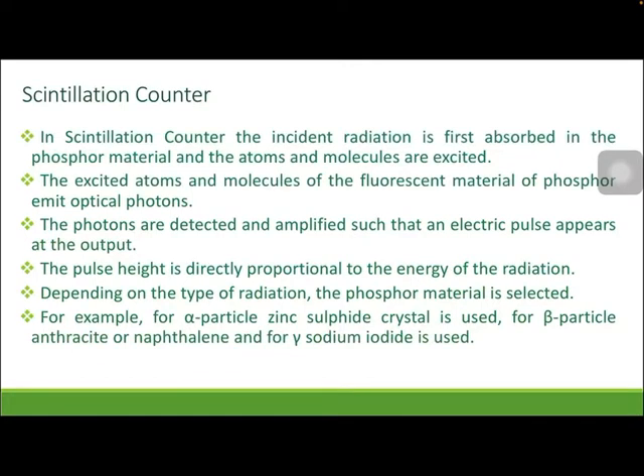The principle of the scintillation counter is: the incident radiation is first absorbed in the phosphor material and the atoms and molecules are excited. The excited atoms and molecules of the fluorescent material of the phosphor emit optical photons, which are light flashes. These light flashes are called scintillations, and therefore it is named the scintillation counter. The photons are detected and amplified such that an electric pulse appears at the output. The pulse height is directly proportional to the energy of the radiation.